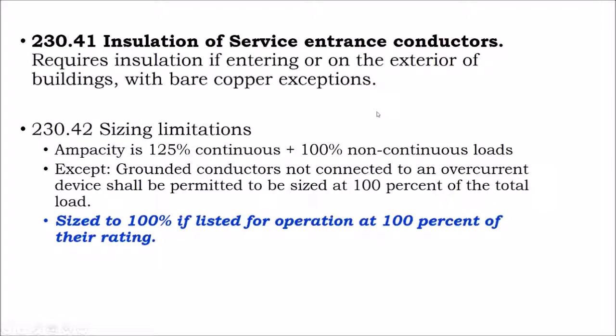All right, so for service conductors, their sizing is based on 125% of continuous loads plus 100% of non-continuous loads. And then it says grounded conductors not connected to overcurrent devices shall be permitted to be sized at 100% of the total load. What that's saying is that the neutral wire, if it's not connected to an overcurrent device, is permitted to be sized at 100% of the load with no additional 25% allowance for the continuous load. And what that means is there are situations where the neutral line can be undersized, and it might save the client a little bit of money. However, in solar, you're generally not undersizing the neutral just to avoid any mistake for the time being.